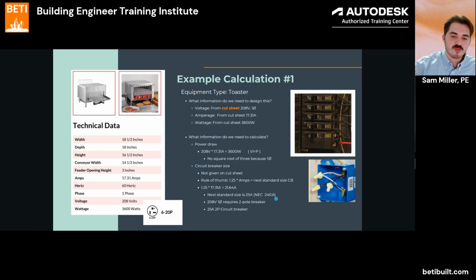But again, this is why it's important to make sure that we're designing around real equipment and not just saying, oh, this is the 27 amp circuit breaker, because you're not going to be able to get one of those. So for this one, we would have 17.31 amps times 1.25, 21.64 amps. The next standard size is 25 amps. Then we can go back into Revit. Simply click here, 25 amp circuit breaker. It'll show your appliance load classification that you assigned down here, your demand factor there. And now we are rocking and rolling inside this panel schedule.